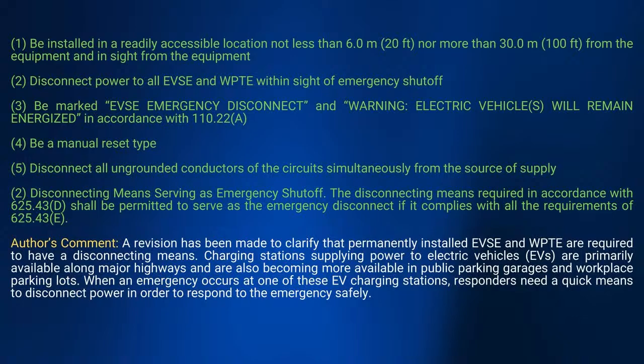But they've got to be within sight and within 20 foot, no more than 100 foot. And then it'll be marked EVSE emergency disconnect, with a warning that electrical vehicles will remain energized, which you should know that anyway.